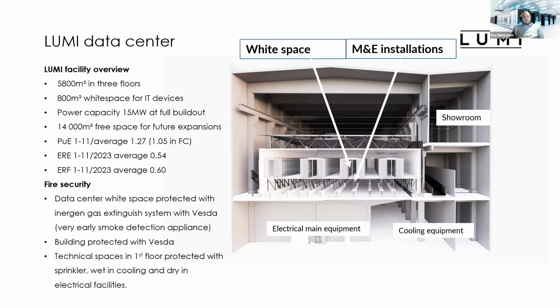Some numbers about this year, so these are from January to the end of November. Our PUE average is 1.27, and we are able to operate down to 1.05 PUE in free cooling. But this PUE is increased because we are operating the heat pumps ourselves. So the energy reuse value average this year has been 0.54, and the energy reuse factor is 0.6. So for every megawatt that we spend, we are able to reuse 600 kilowatts of it.